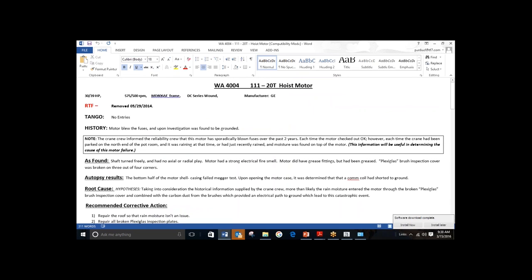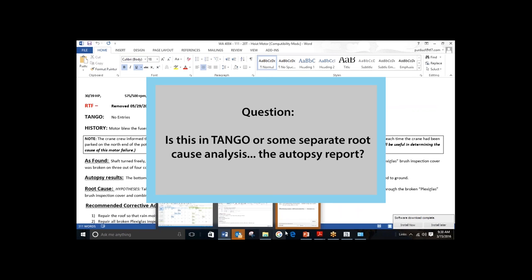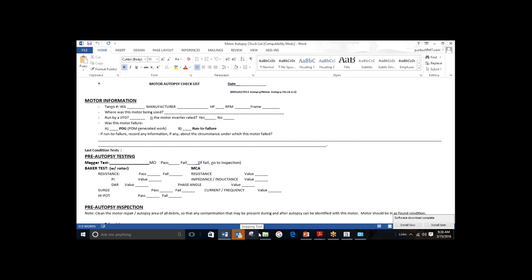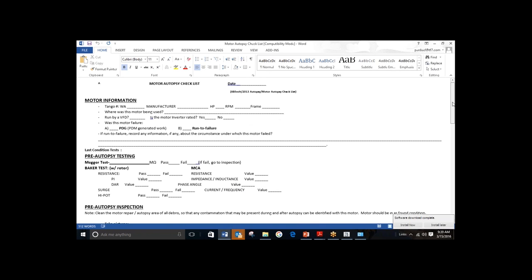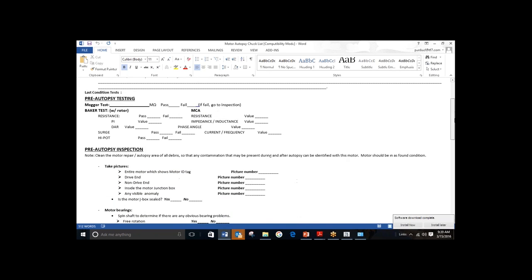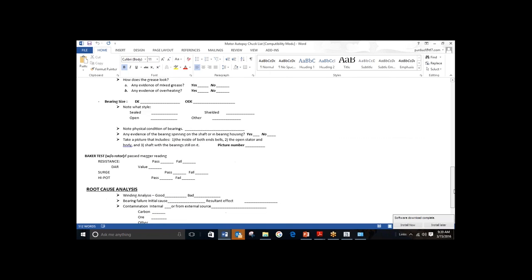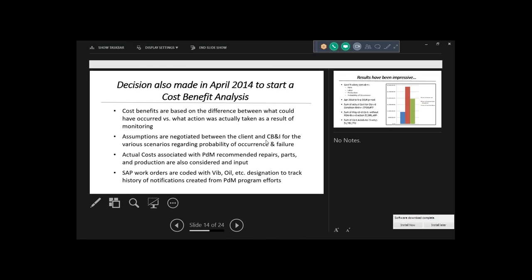We actually went out and tried to identify the root cause of the motor failure. When they were just replacing motors without any history, we determined whether or not it was lubrication, cleanliness, motor fatigue. All those items were not being captured as history as why the motor failed. When we got that information, we were able to determine what needed to be approached and how to approach it to reduce the number of failures. The next heading is make sure you get an autopsy on all the critical equipment failures. I don't know why it's failing. You have a winding failure in a motor and the plant says the windings failed. When you get to the shop, the windings failed because it had water in the windings. Obviously, your problem is sealing and water, not winding. So you've got to get to that root cause.